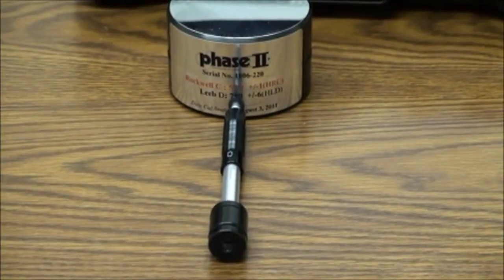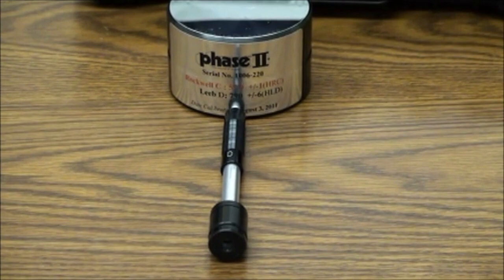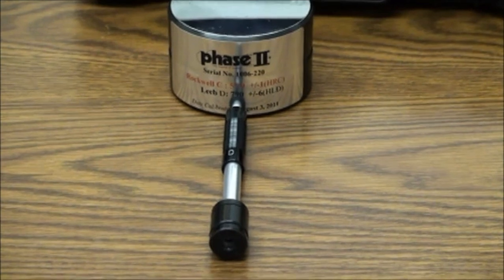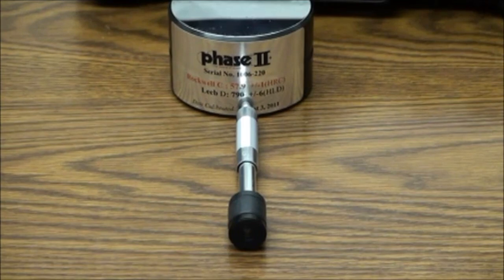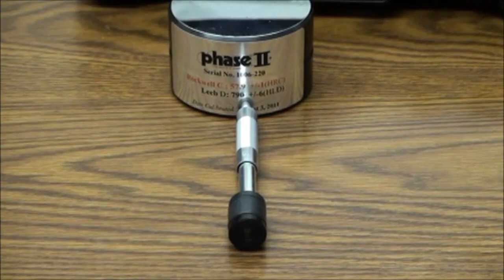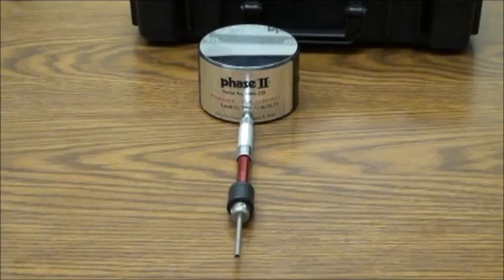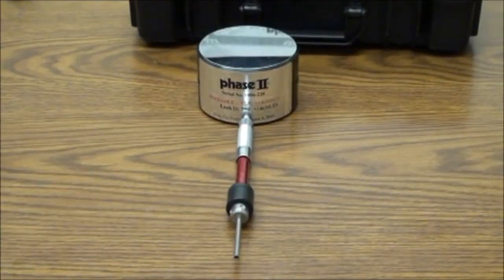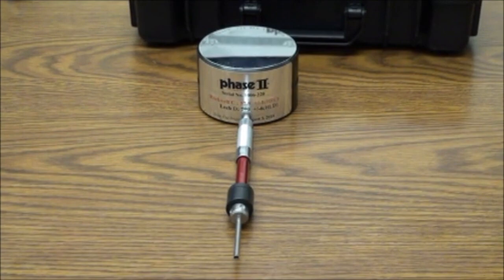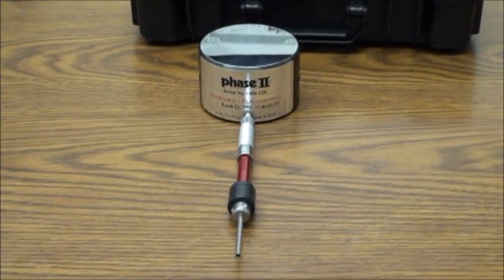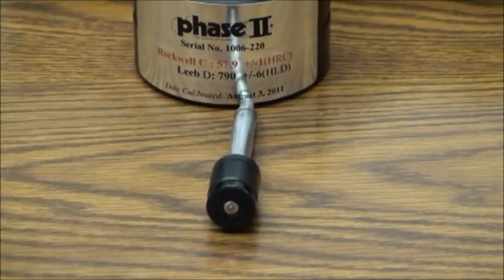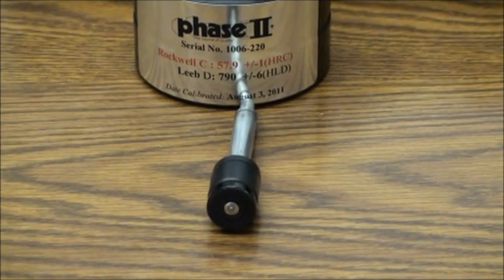All Phase 2 portable Leeb hardness testers have available the following probes for various applications. The D probe is a general purpose probe and comes standard on all models. All other probes are available as options. The C probe is a reduced energy probe for case hardened layers. The DL probe has a needle type tip in order to test in tight places such as gear teeth. The DC probe is short to fit in small bores or confined areas.